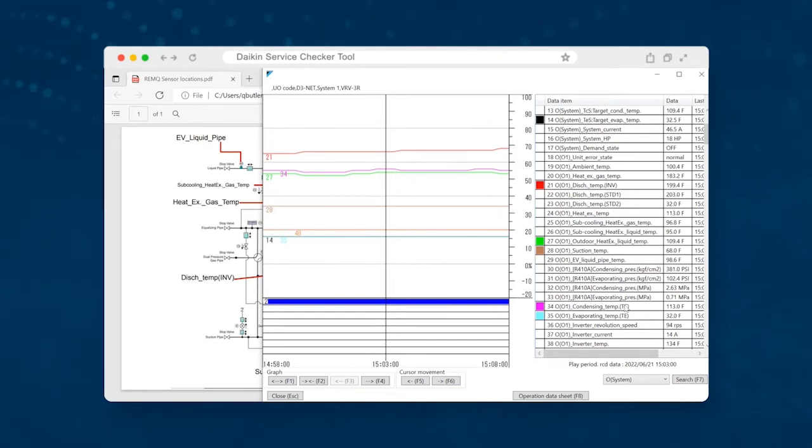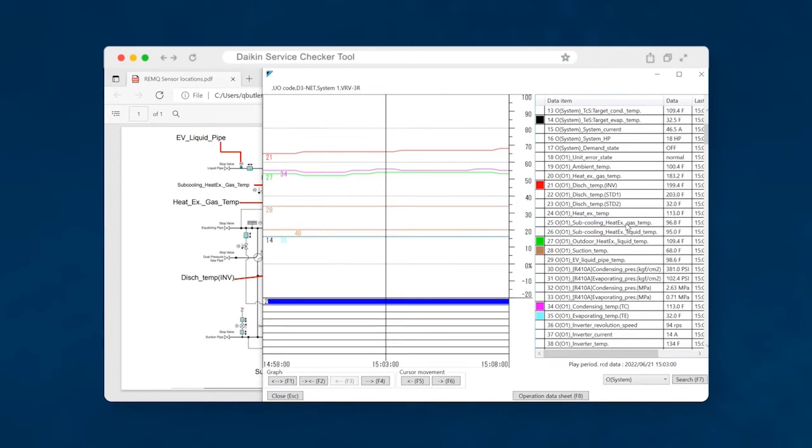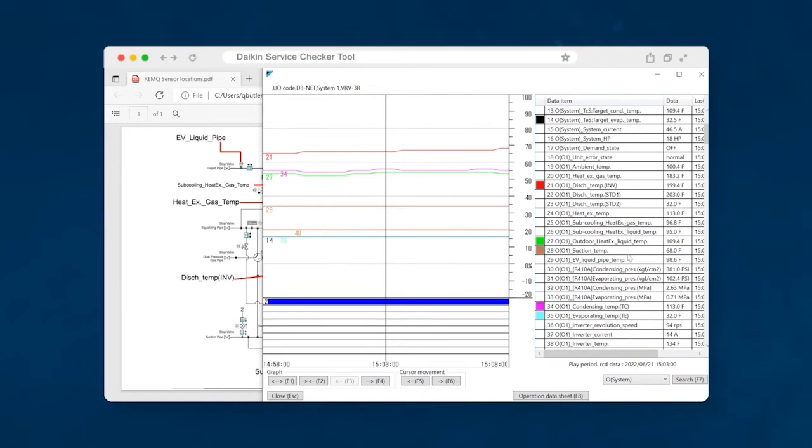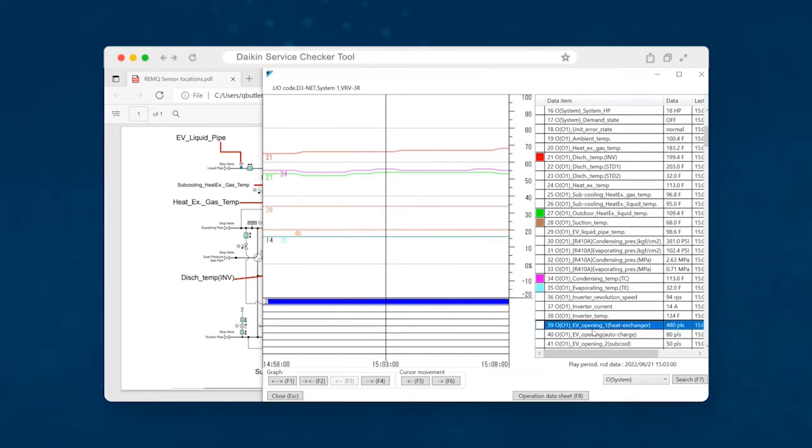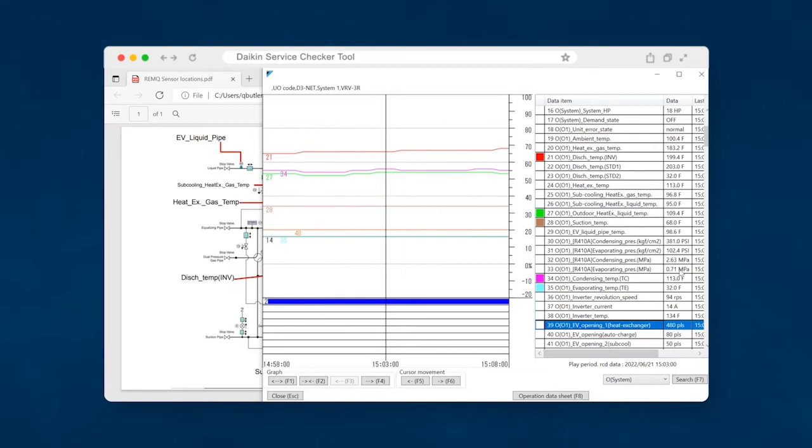So basically, the system is controlling ultimately to target evaporator temperature, and it tries to do that by any means necessary. Now there are some safeties that may come into play, you might see the sub cooling heat exchanger open up, which is essentially in place to help cool down the compressor. And then you can also look at the expansion valve position of that sub cooling heat exchanger here. Right now it's not open very far. This is a 480 pulse scale. And then our main heat exchanger EEV is also a 480 pulse valve, and it's wide open.